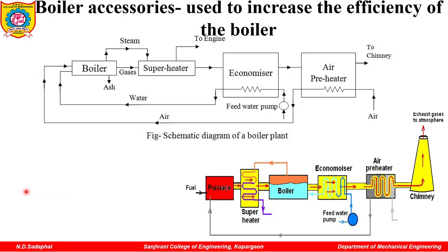What the air preheater will do is extract the heat. These gases are passing to the chimney, to the outside, so the heat of those gases does not have any importance. So the air preheater will extract that heat from the hot flue gases which are leaving through the chimney. Then that heat will be supplied to the furnace. So to burn the coal here, the energy required will be less because this heat is supplied. So ultimately, you require less energy to burn the fuel.